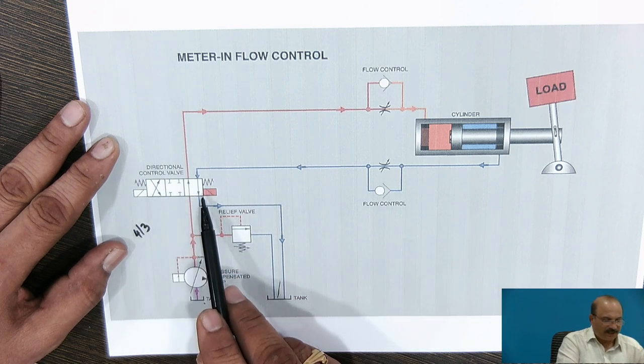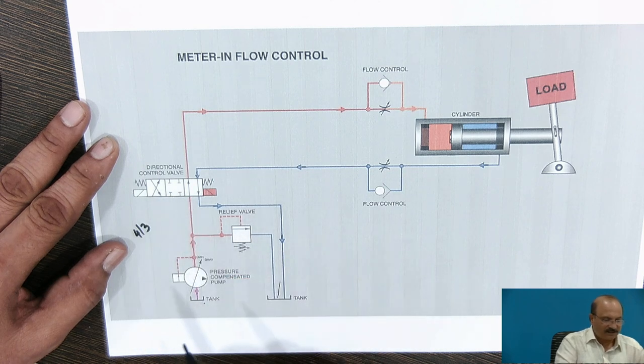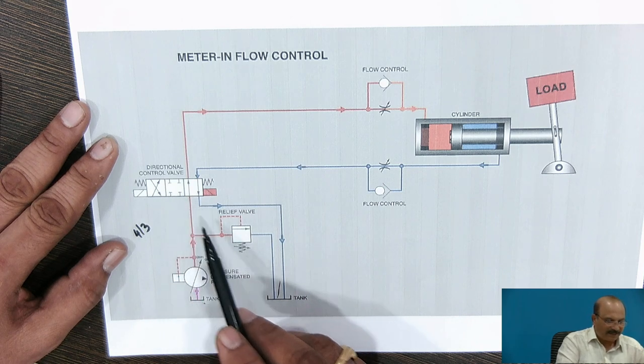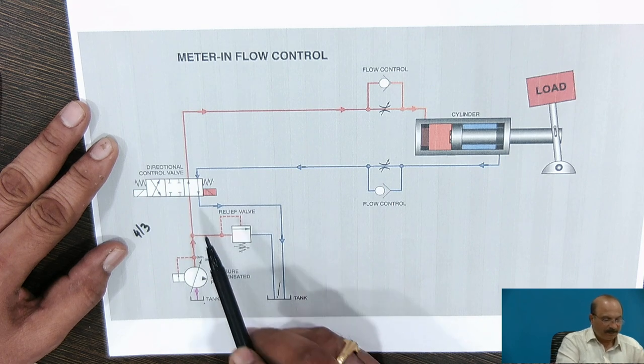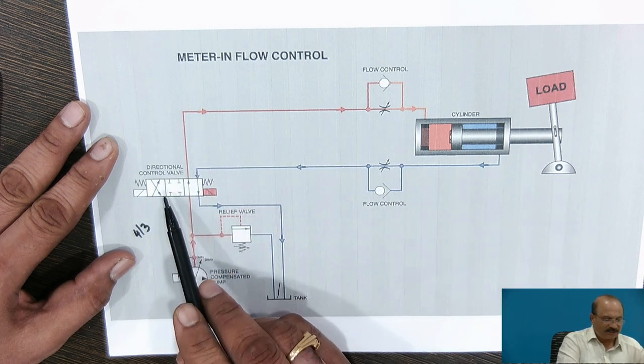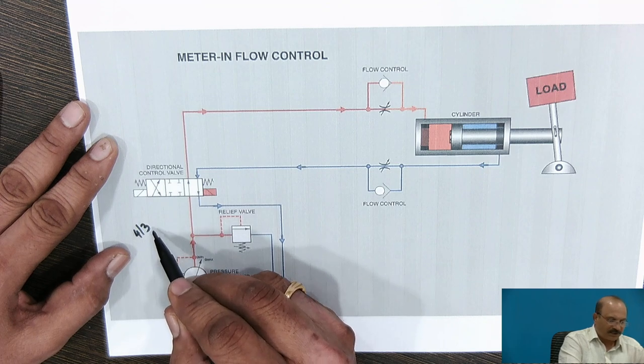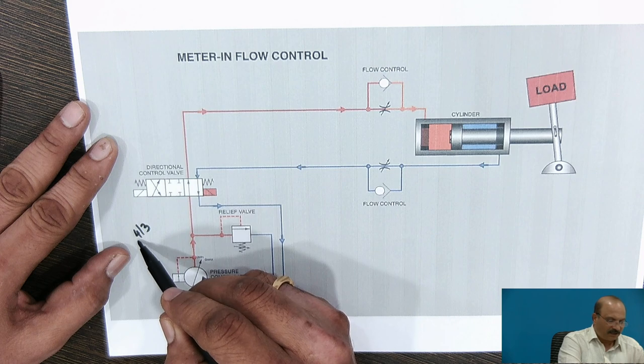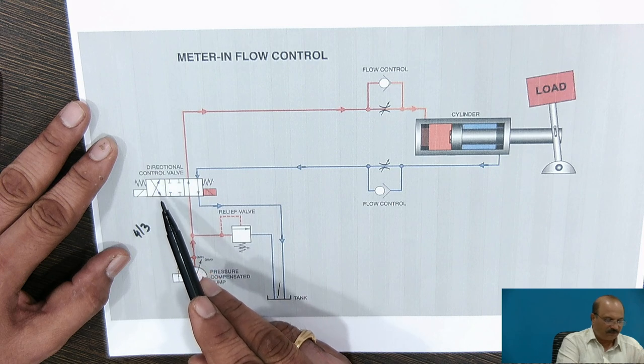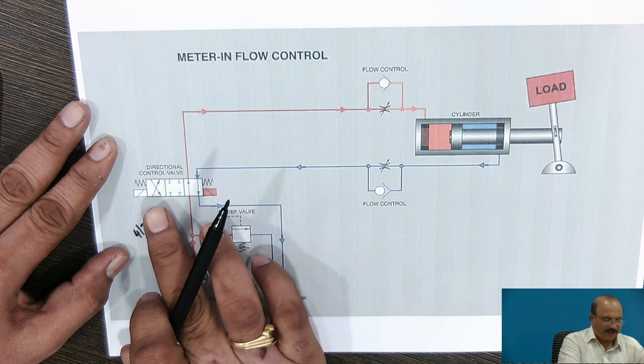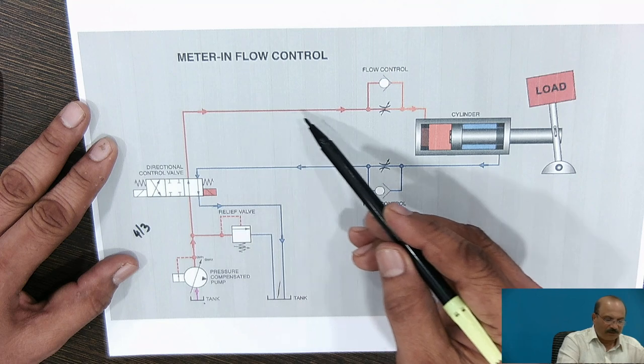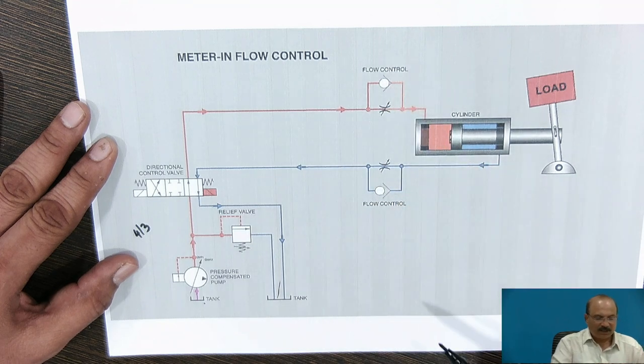Whenever we operate this knob, we can control the flow. The middle position is related to normal flow — whatever flow is there will come back to the storage tank. In this diagram, we have connected it for flow in the upward direction. So we are calling it a 4 ports and 3 positions directional control valve — the first number is related to the 4 ports and the second to the 3 positions we can change.